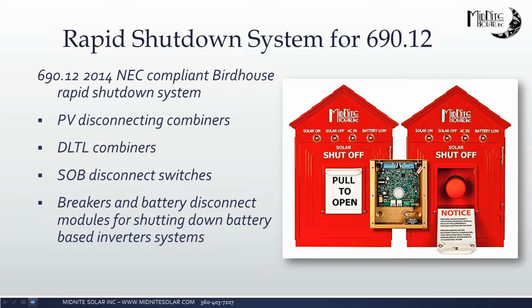So the birdhouse is an integral part of all of this as far as 690.12 NEC goes. Rapid shutdown. The birdhouse is our 2014 NEC compliant solution. It interfaces with all of those combiners or SOBs or DLTLs we talked about earlier. It'll also interface with the battery breakers that Sue talked about that were remote trippable and can be used to isolate, say, a generator, which you'll see in a minute.